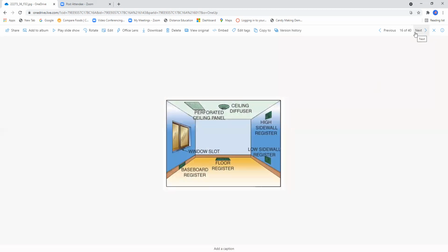Okay, here we have an illustration showing the different locations. This is going to be found on page 1078 of your textbook, and it gives you locations depending on the type of system, as far as where the air is going to get distributed. Typically for air conditioning, the best way is either up here on the ceiling or a high sidewall. Low sidewall is not technically ideal for a supply situation. It is great for heating. A floor register, again, is great for heating. I wouldn't say it's great for cooling. And baseboard registers also work well for heating. I'm not wild about them as far as air conditioning.